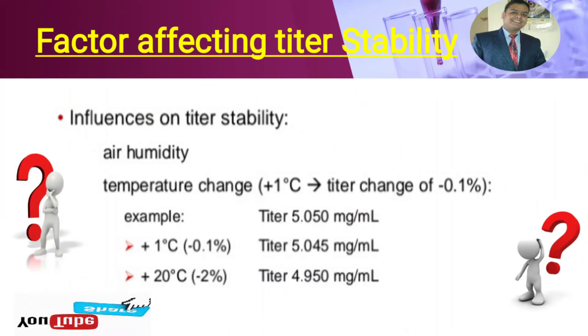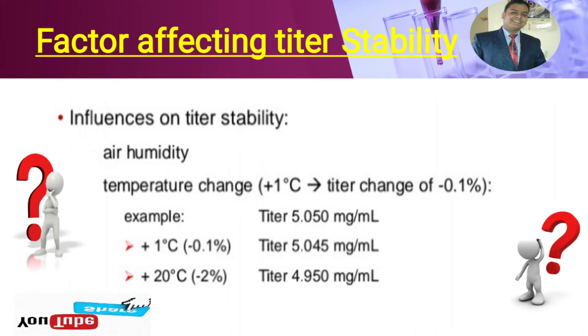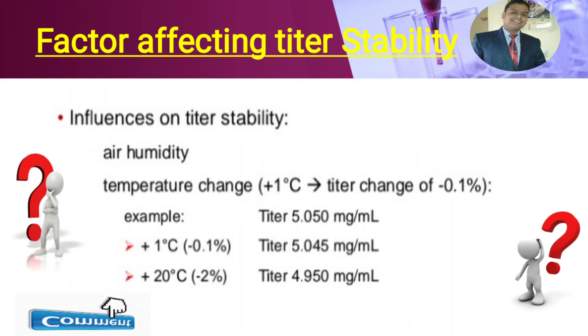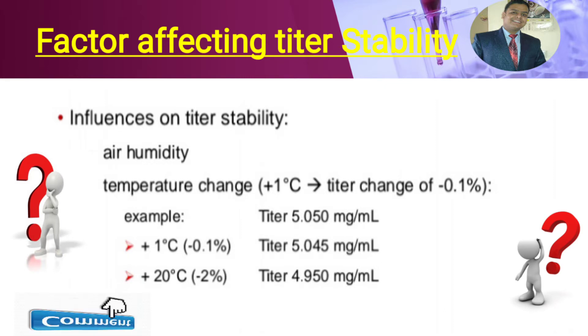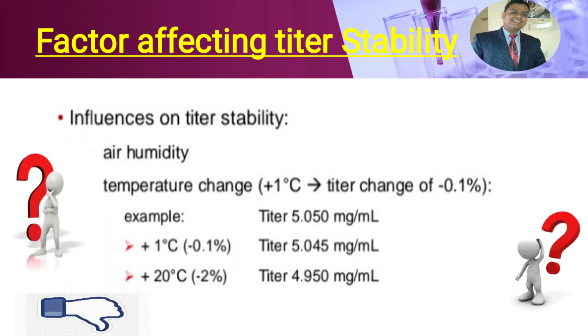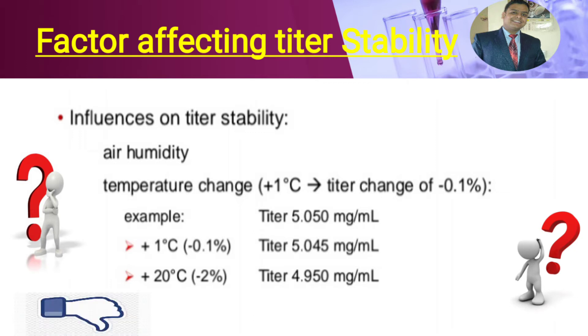Factors affecting titer stability are shown on the screen. The KF reagent is influenced by air, humidity, temperature, and light. A 1-degree increase in temperature reduces KF factor by 0.1%. For example, if we have the factor 5.050 mg per ml and we increase the temperature by 1 degree, there will be a decrease of 0.1%. If we increase the temperature by plus 20 degrees Celsius, there will be a decrease of minus 2% in the Karl Fischer factor.